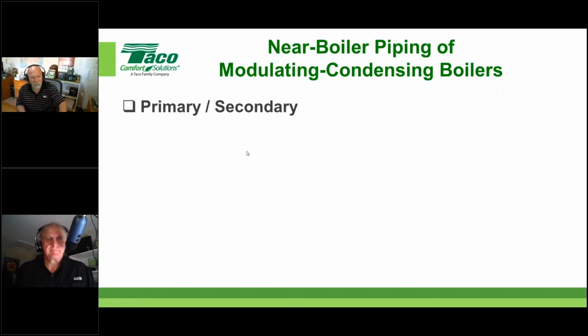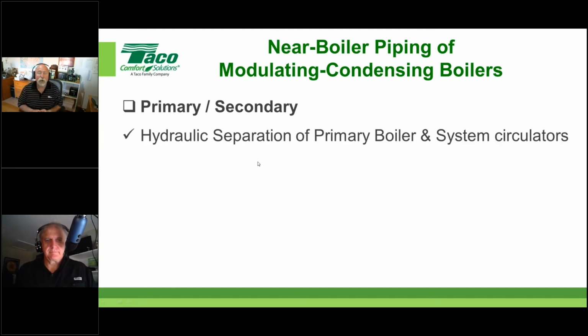But generally speaking, if we're going to pipe in primary secondary, what does it give us? And John touched on this already, right? What we want is we never want those two circulators, let's say it this way, the system circulator and the boiler circulator, ever affecting one another. The way that we do that is we achieve hydraulic separation. This is what we're talking about right here. We want those two pumps to never associate with each other.